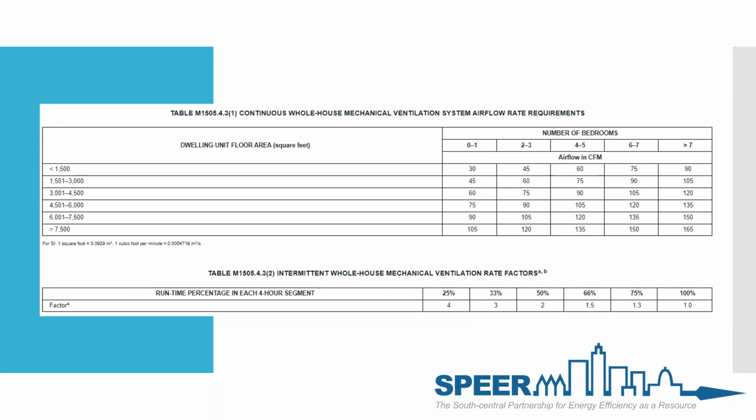With third parties, most of you guys, if you're testing it now and you're able to adjust it, if it's supposed to get 75 and you test it and you're getting 150, well, then you basically turn the run time down to 50%, half the time, 30 minutes out of every hour.